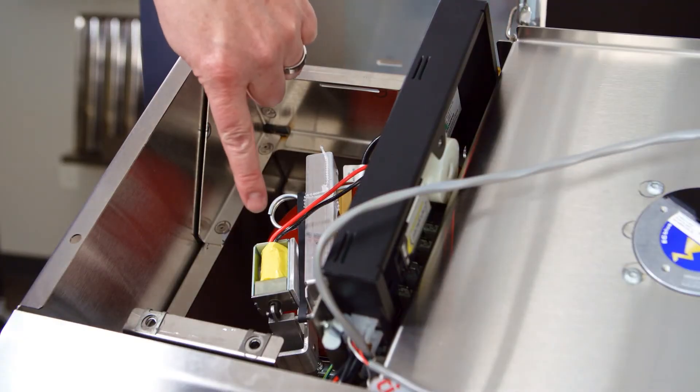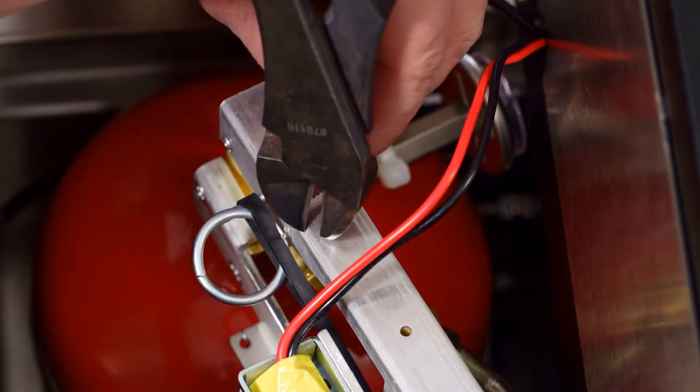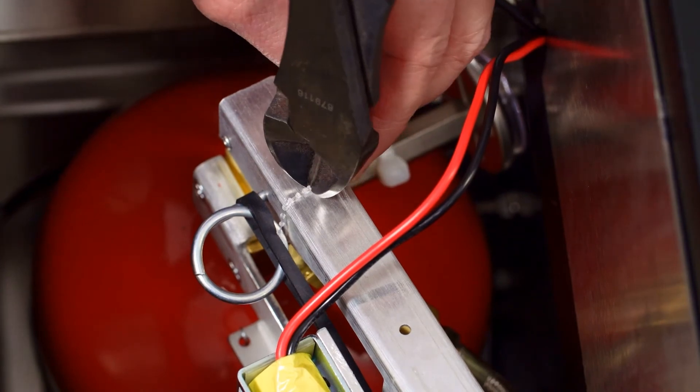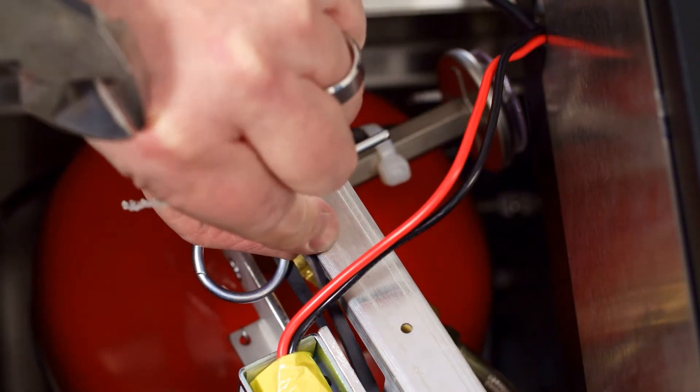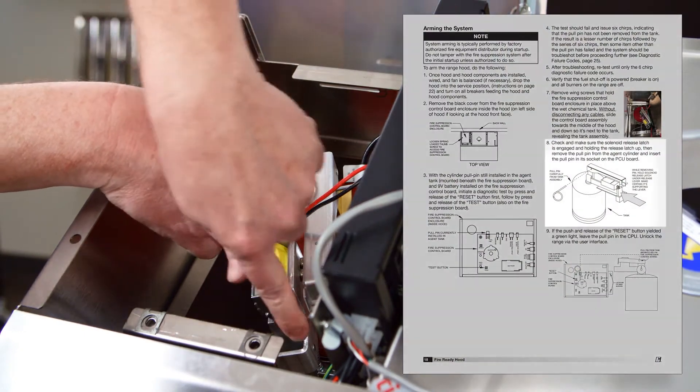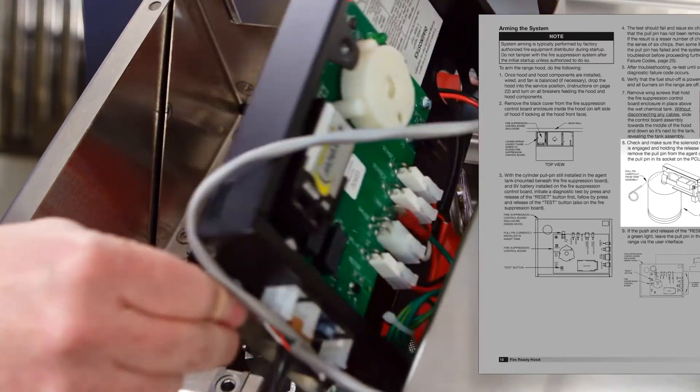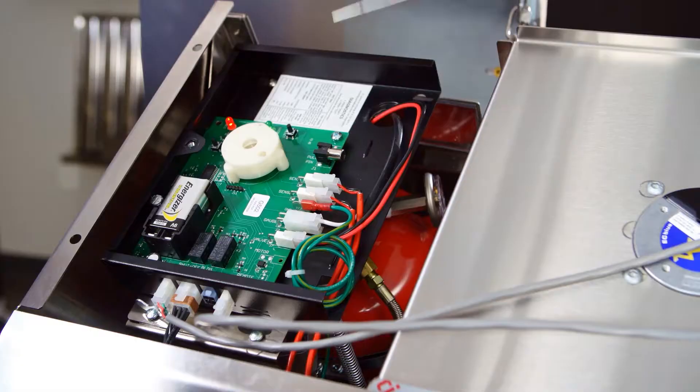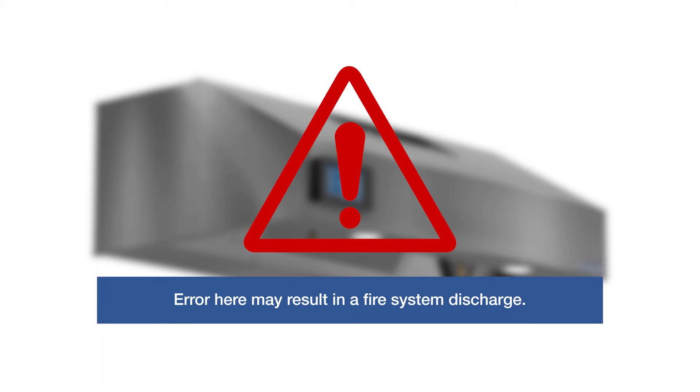Check and make sure the solenoid release lever is engaged and holding the release latch up. Then carefully remove the pull pin from the suppression tank. Insert the pull pin into its socket on the control board. Once the pin is removed, the fire system is armed, so pay close attention when performing this step as an error here may result in a fire system discharge.